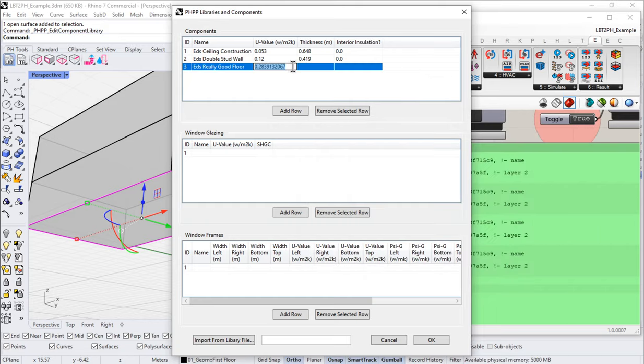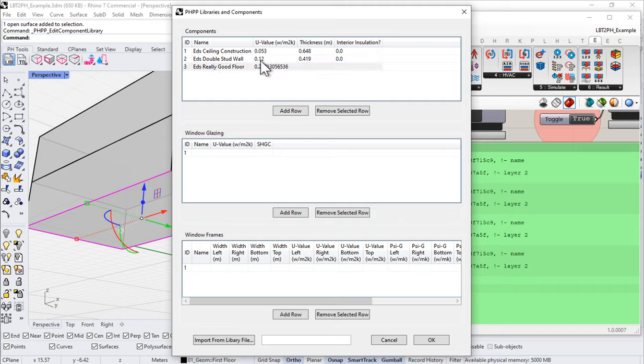Let's say an R-25 floor. One over the R-value gives the U-value — so 0.04. I come into the U-value field and say 0.04, but notice I have to input in watts per square meter degree Kelvin. So I enter that in IP units and when I hit enter it'll do the conversion for me. I can do the same with the thickness.